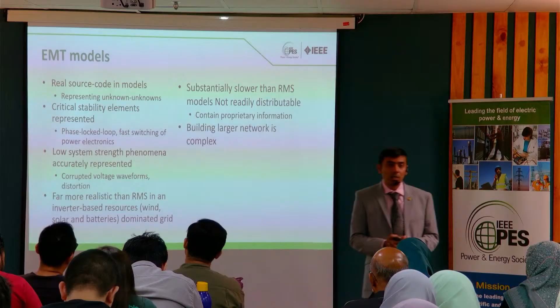Critical elements such as phase lock loop and fast switching transients of power electronics can be captured in EMT models, including corrupted voltage distortion. These are things RMS models don't capture when a fault happens. In RMS, voltage just goes down and comes back up, but actually all three phases are corrupted during the fault, and even afterward you wouldn't see steady state immediately. All these features can be captured in an EMT model.